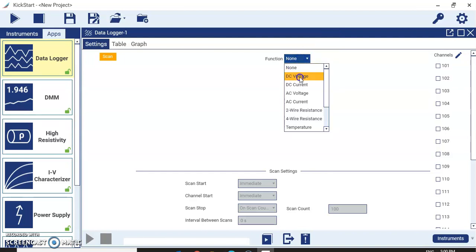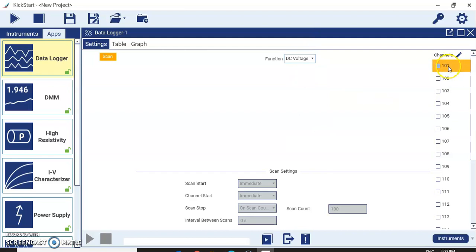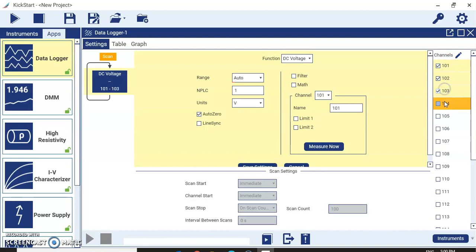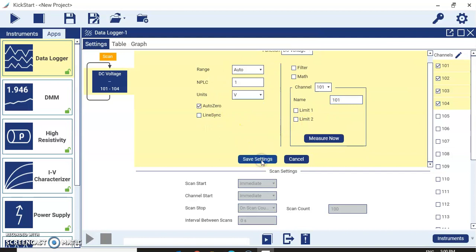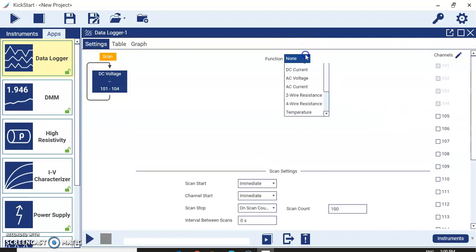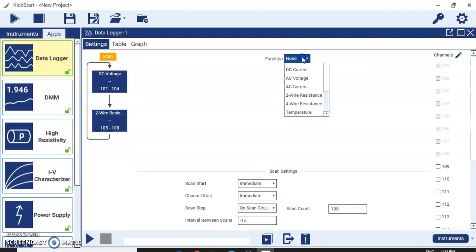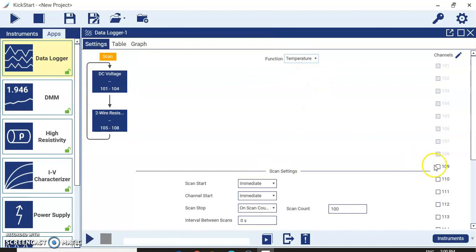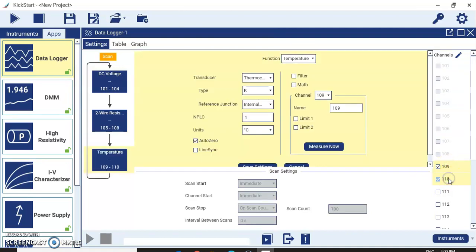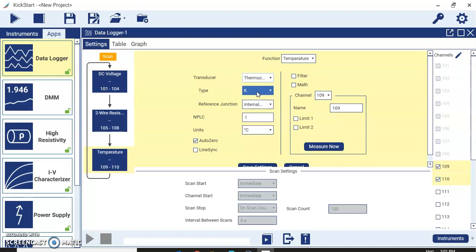I will select DC voltage for channels 1 through 4, then set two-wire resistance for channels 5 through 8 and save. I will also select temperature measurement for channels 9 and 10, where I have connected thermocouples. You can choose thermocouple, thermistor, or two-, three-, or four-wire RTD. I will select K-type thermocouple, set the units and NPLC, and save the setting.